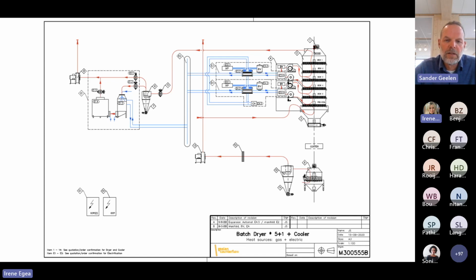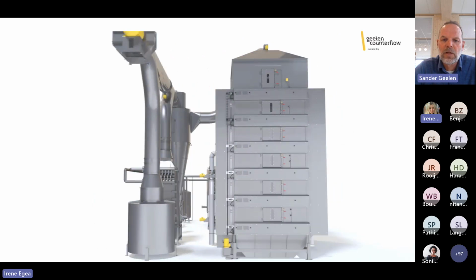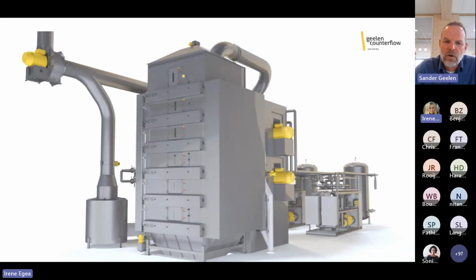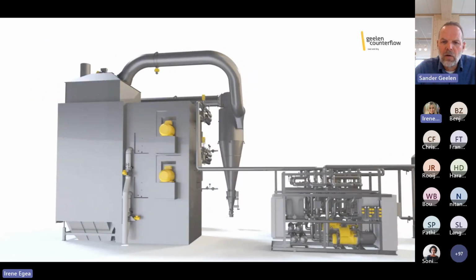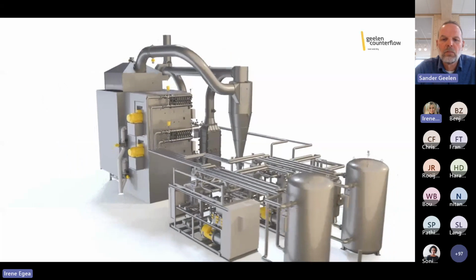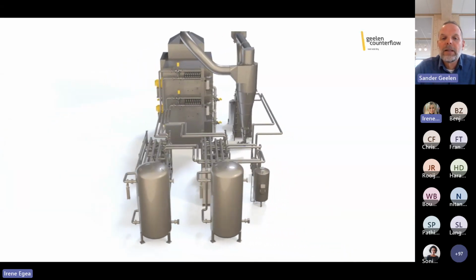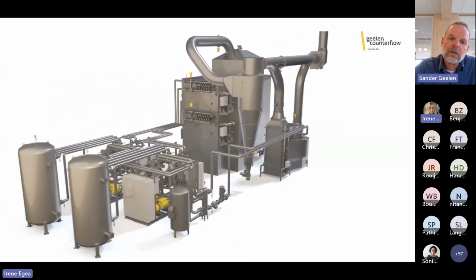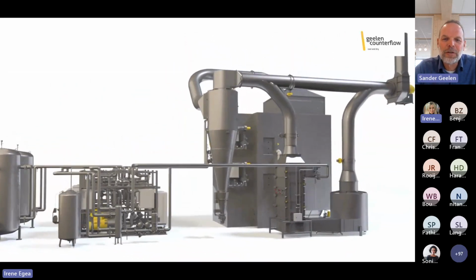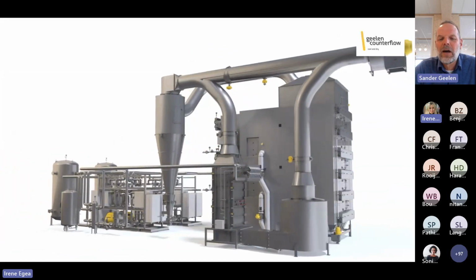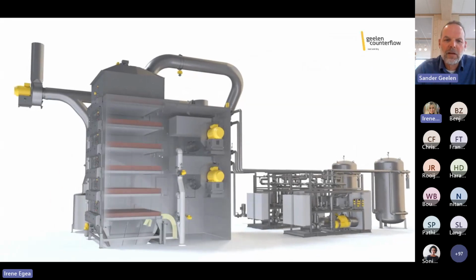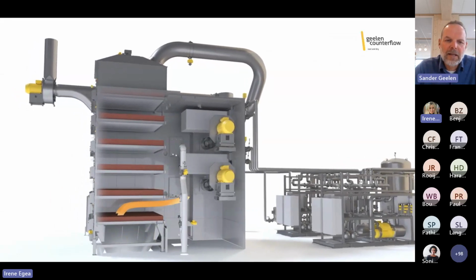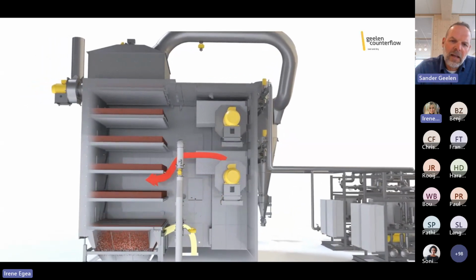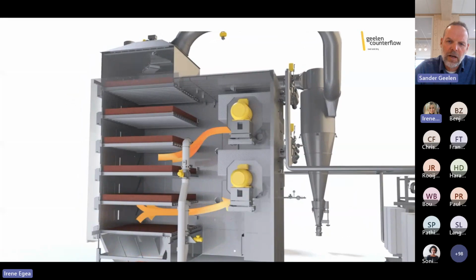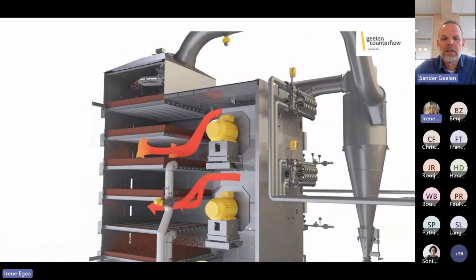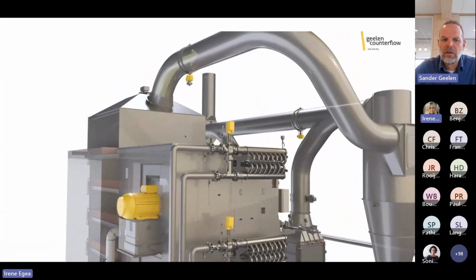Now, if we go to the next slide, please, then you will see an animation of how that system looks like. In this example, in a 6-stack dryer, and we're running around the dryer now, and you see at the back the two heat pumps in the flow diagram, the two buffer tanks that we're looking at right now. And then in a minute, when we go to the next slide, I'm sorry, Irene, we just wait for this animation to move on. Then you will see in a minute how the energy is passing through the dryer. You see here the decks where product is contained, and air is flowing through each of those decks, typically the hot air. And that used to come from gas burners or steam heat exchangers. Basically, that part of the system is not different.